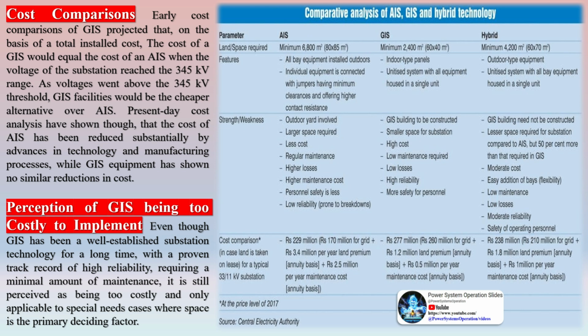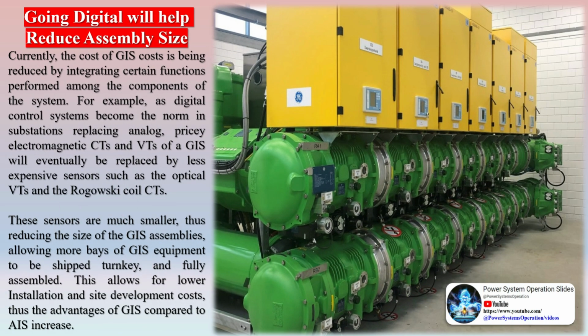Even though GIS has been a well-established substation technology for a long time, with a proven track record of high reliability, requiring a minimal amount of maintenance, it is still perceived as being too costly and only applicable to special cases where space is the primary deciding factor. Currently, the cost of GIS is being reduced by integrating certain functions performed among the components of the system. For example, as digital control systems become the norm in substations, replacing analog, pricey electromagnetic CTs and VTs of a GIS will eventually be replaced by less expensive sensors such as optical VTs and Rogowski coil CTs.